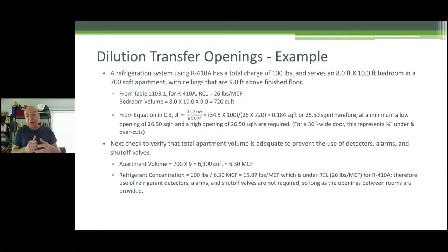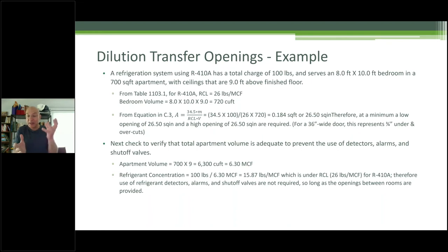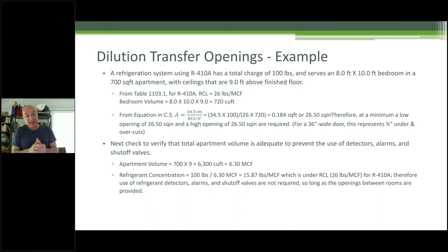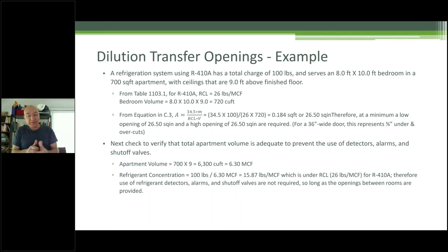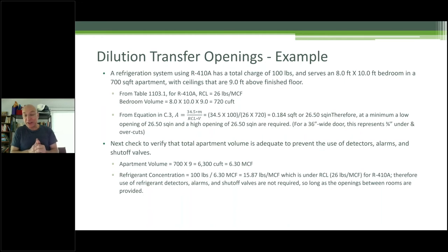After providing the undercut, we have to verify the total apartment volume. You provided an undercut because we exceeded the RCL for that room — fine. But for the apartment at 700 square feet, apartment volume is 700 times 9 equals 6,300 cubic feet. Refrigerant concentration: 100 pounds divided by 6,300 cubic feet = 15.87 pounds per 1,000 cubic feet, which is under the RCL of 26. We're good.